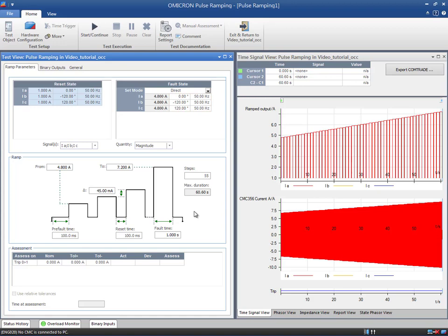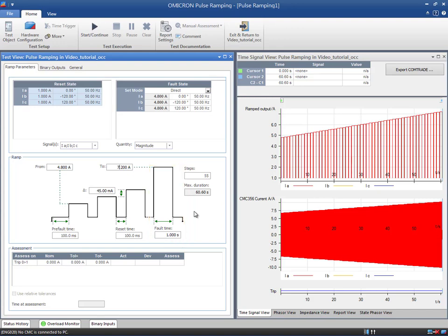The fault state must be shorter than the trip time of the first element, but it must last longer than the trip time of the element you want to test. Therefore, it has to be a middle ground between 100 and 500 milliseconds. Let's say, for example, 300 milliseconds.